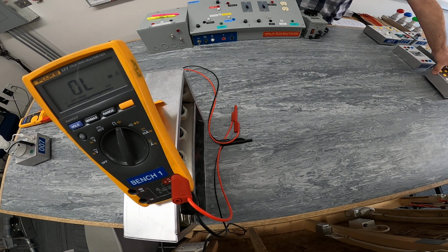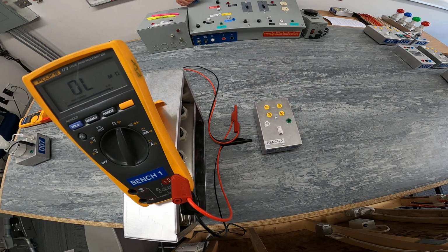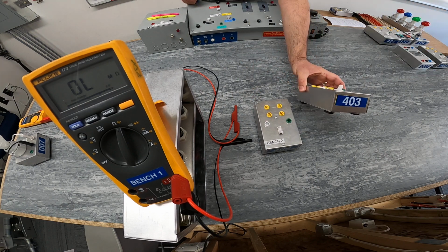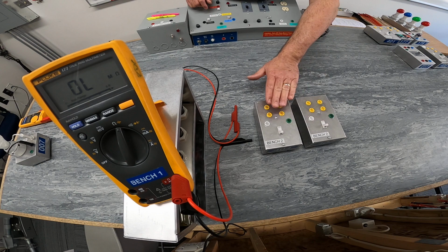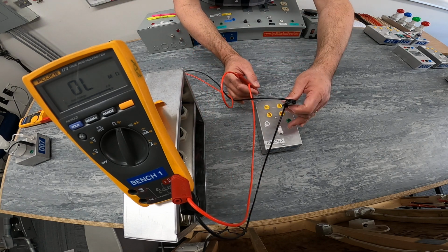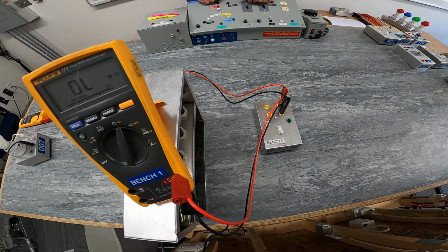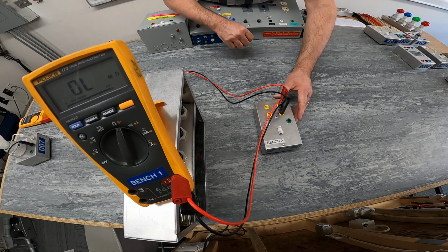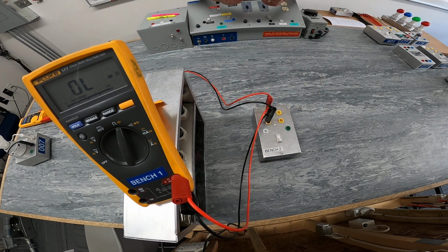perfect. Well, I have a different switch now, referred to as a 404, and as you will notice, it has the same terminal connection. What you see in the 403, it looks identical. So you would think this one should have the same connections as this one here. Well, let's just verify that by taking our leads, and the switch is in that position there. We'll start with this side here. We have no connection, so that is an open. I'm going to leave the switch position where it is. Let's go to this side. We also have no connection whatsoever there.